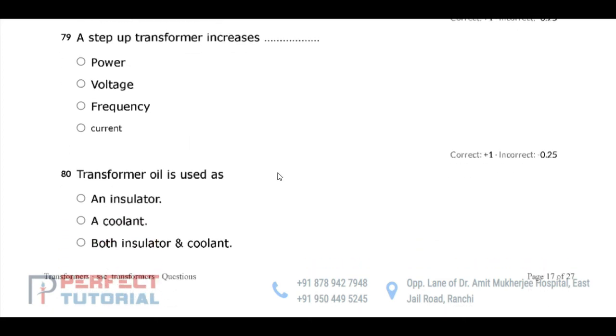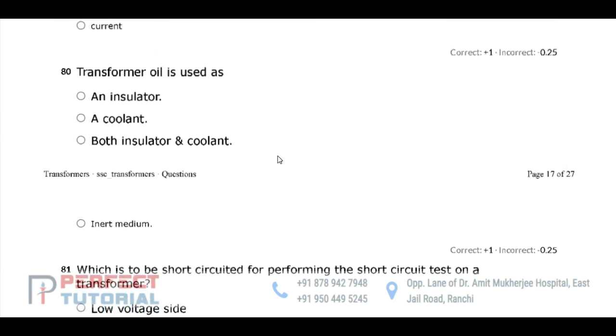Next, a step up transformer increases. See, a transformer is a constant power device. Whether it is a step up transformer or a step down transformer, irrespective of that, it's a constant power device, it's a constant frequency device. So a step up transformer increases voltage level. Next, transformer oil is used as. See, transformer oil is used to provide both the insulating property as well as the cooling property, meaning it is used as both insulator as well as coolant.